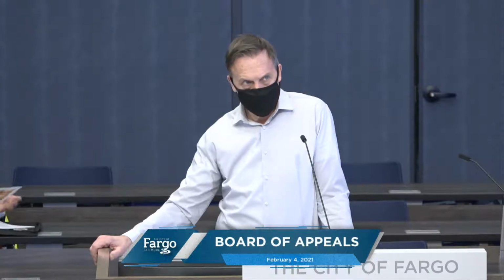Yeah, and I don't see how you could not separate the garages from each other as well. I mean, if you stack 8 of these in a line, you're creating a condition where a fire can go between the garages, and how is a fire department supposed to get in there and put out that large of a fire within a certain amount of time too, in order to not go through 1 hour barriers in other areas and cause other issues. So I don't think you can ignore the 1 hour requirement between the garages. I just don't see that.